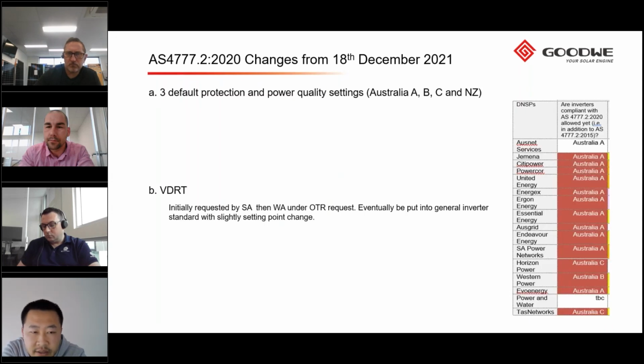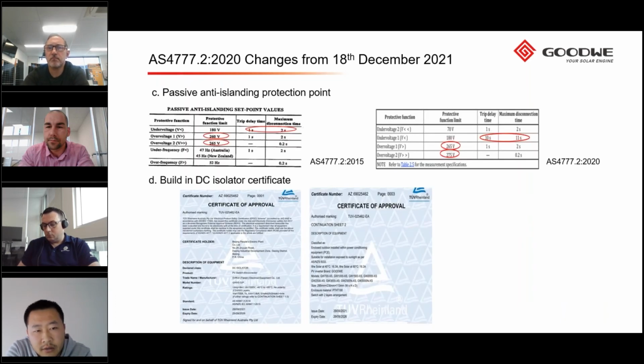Another big difference is that previously we didn't have a VDRT function request. Early this year, starting from South Australia, followed by Western Australia, they have more requests for inverters to support voltage disturbance ride-through, and then the new standard puts this into the inverter standard, requiring the inverter to have this function. Some other changes: the new standard has wider grid connection setting points compared with the old one. For example, the overvoltage action point in the old one is 260 volt and the new one is 265. And the old level 2 overvoltage protection is 265, while the new one will be 275.